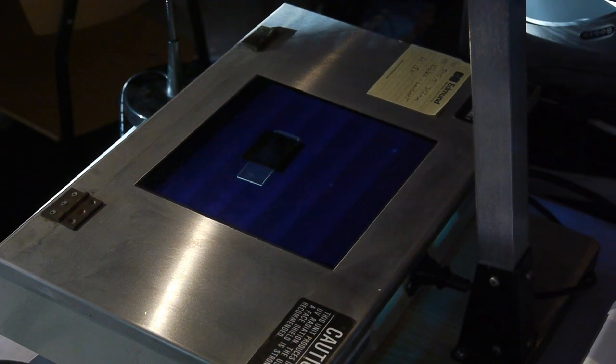The ultraviolet lamp is an electrophoresis illumination system. If you're doing DNA analysis, some of the dyes used are fluorescent in UV. You would put the gel on top of this thing, and it would light it up with UV light. The device has six 15-watt UV lamps in there, and they peak at 312 nanometer.